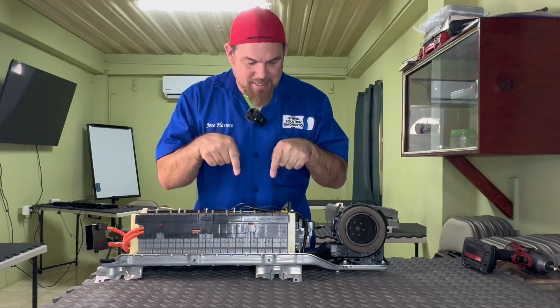Look at the level of corrosion between the connections, and this is exactly the problem over time. If there's a high amount of current flowing between one battery and another in order to make the vehicle drive, and then you add lots of high resistance due to the corrosion, that is going to make the battery, especially here in the middle, heat or overheat. Because of that, the modules lose capacity, hence they discharge faster than one another. That's how the battery goes unbalanced, losing overall capacity.